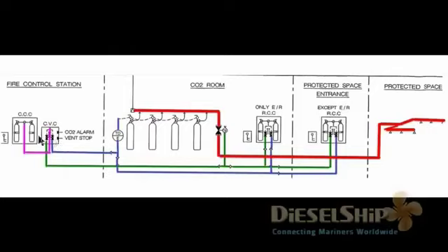And I'm going to open one of these bottles, and there is a pressure gauge here. Once I open the bottle, I get a pressure indication over here, and just follow the pink line. It goes to the two valves, and after that it waits for the chief engineer to operate it. And once the chief engineer operates both these valves, after confirming that the vent fans have stopped, quick closing valves are closed, and the dampers are shut, etc., etc.